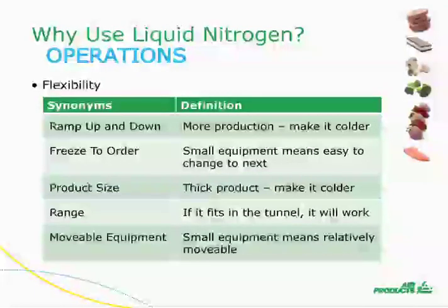The flexibility of liquid nitrogen systems stems from its extraordinary cold: 320 degrees below zero. This allows liquid nitrogen systems to operate across a broad range of temperatures, from simply cool to hundreds of degrees below zero. You are able to ramp production up and down — the liquid nitrogen use simply follows the pattern. You can freeze to order, and smaller equipment makes this much easier. Different product sizes work well by simply making the equipment a bit colder or using a bit more nitrogen. A broad range of products are possible; again, the turndown of liquid nitrogen allows for this.